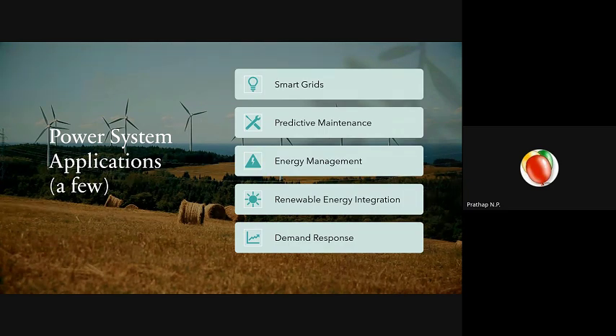Now, how you do demand calculation is you add all the loads together, and then you put something called a diversity factor or demand factor, because let's say you have a light. The light bulb does not glow 24 hours a day. Say, this is the demand of my facility, and you would give it to the utility, and they would charge you based on that. Now, demand can increase because you might add another section, or you could expand your building. So every 5 years, the utility requires us to submit a revised calculation. All this has been happening for so many years. This is how static demand calculation happens.